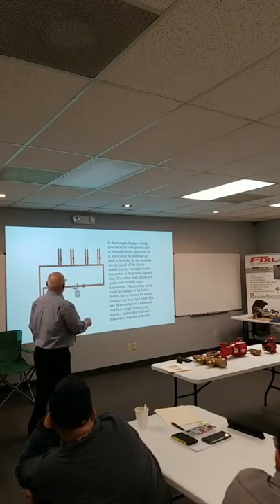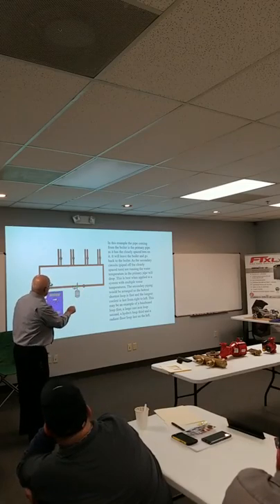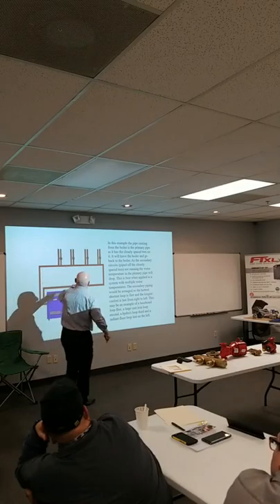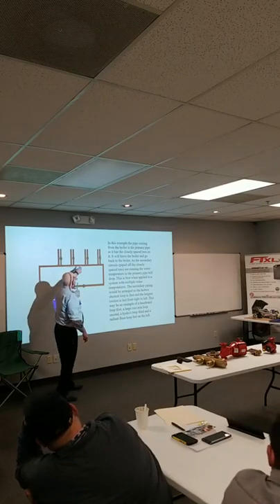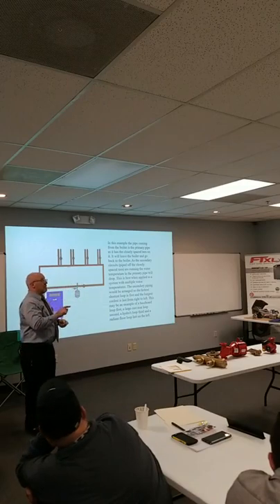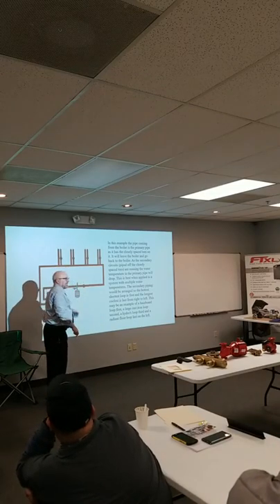Yeah. But yeah, see, these pumps are doing the same thing. This is the direction of flow. Right. So my direction of flow is going this way. I want this secondary loop. So the true meaning of primary, secondary is this. The larger pipe is the primary. The smaller pipe is the secondary. Primary is the heat source, secondary is where the heat goes. No. That's boiler loop, system loop. Primary and secondary. So right now, this is primary, that's secondary, right?